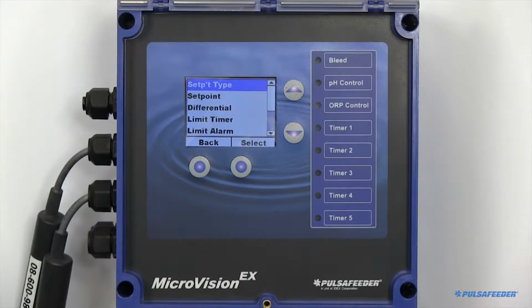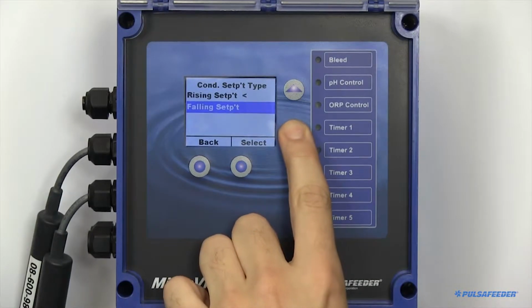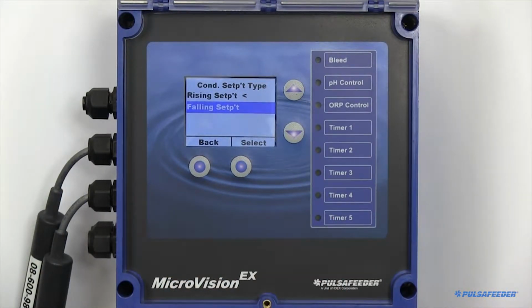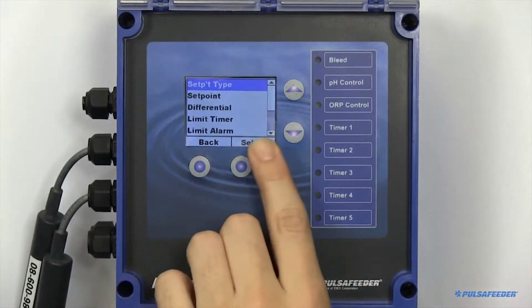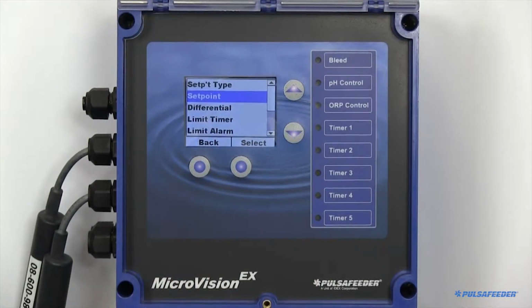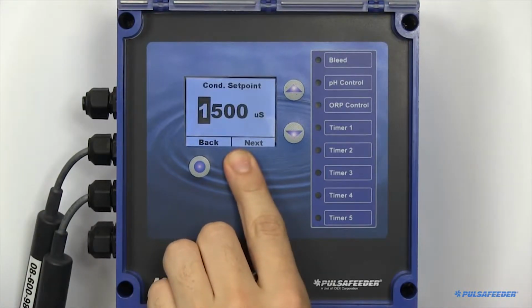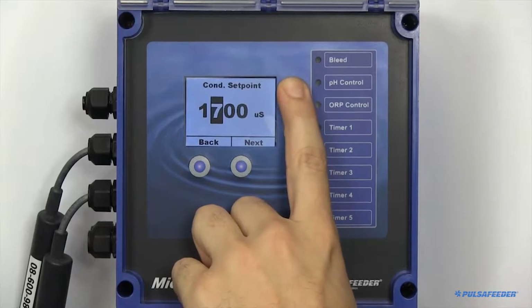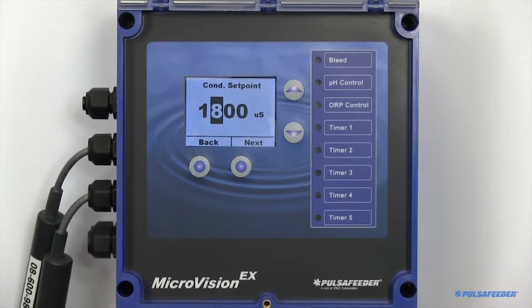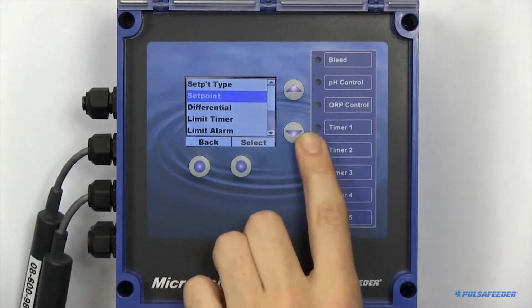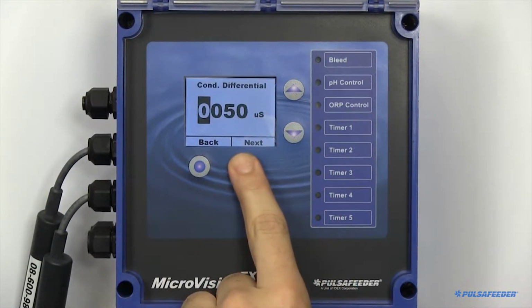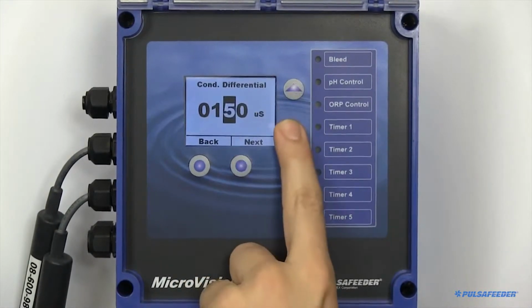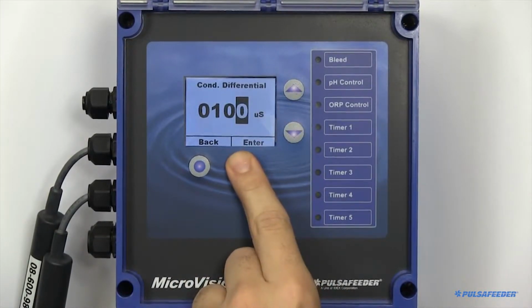To set up your conductivity probe, you choose your set point type. You can choose between rising or falling. Rising type means that the output activates when the input goes above the set point. Falling type activates the output when the value goes below the set point. Your set point is where the desired function will begin. The differential, or deadband, is the offset value which must be satisfied before the relay will turn off.